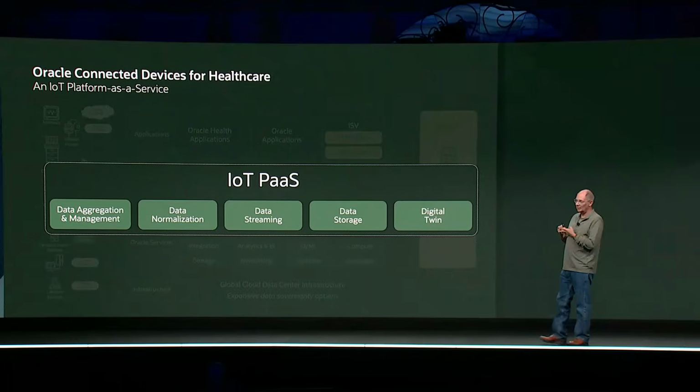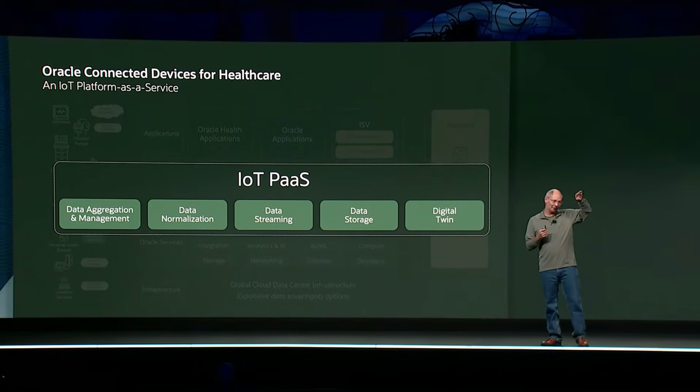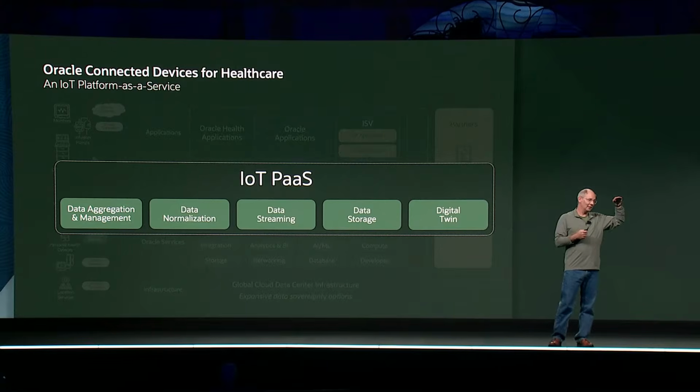Two, we collect the temperature on a regular basis. So if a fridge goes above a certain threshold, then through the LLM, we can say, okay, which reagents are in that fridge and which ones of those are actually affected by this temperature shift. Lab technician comes in the morning, generates a report: fridge number 4, reagents 1 and 2, you probably want to throw them out.